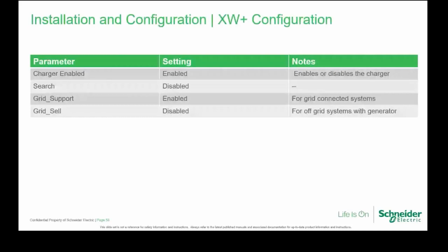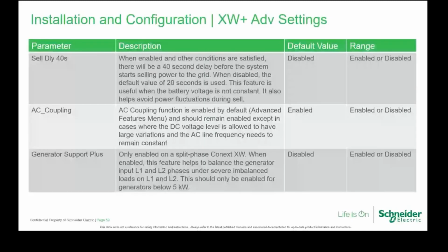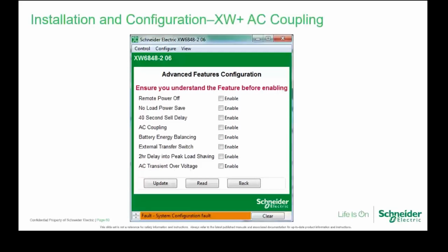I think we went through before: charger enabled, enables the charger, search, grid support only for a grid connected system, grid sell for an off-grid system with generator, that's disabled. These are the settings you might want to put in the advanced settings for the XW Plus. You can delay the sell, that won't make any difference because it will always sell. The one you do need to put in is the AC coupling. Got to make sure that's enabled, okay? Generator Plus, that's different: if you're going to set up line one, line two phase imbalancing, you can set up and enable that if you require. On the configuration tool, you can just tick the box for AC coupling.